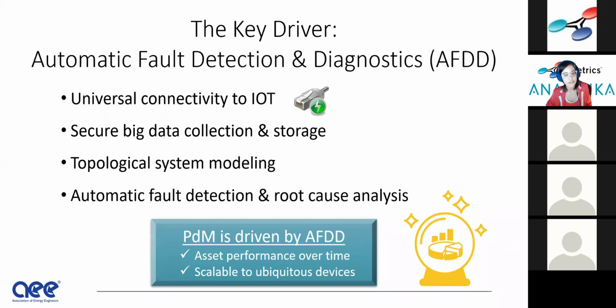This AFDD system, which is what I'll call it, AFDD, this was going to find failures from simple mechanical failures like a valve leaking by or passing, when intended to be closed, all the way up to suboptimal sequences of operations like economizer mode, you know, enthalpy, temperature-based, dew point-based, and other things like issue recurrence, scheduling, you name it. Depends on the points, right? Depends on what we can see. So PDM, which is predictive maintenance, I might call it PDM, we're really utilizing the AFDD here and the data.